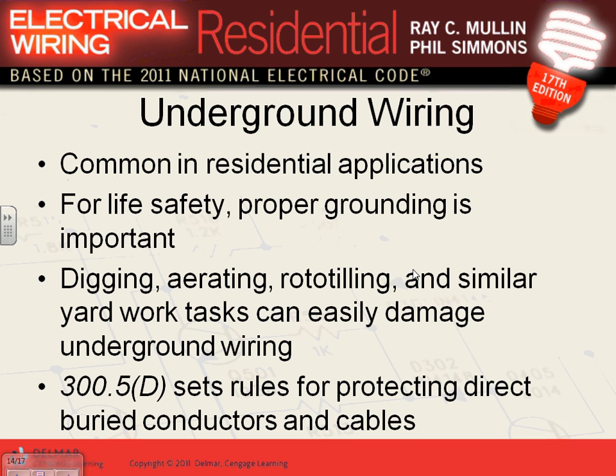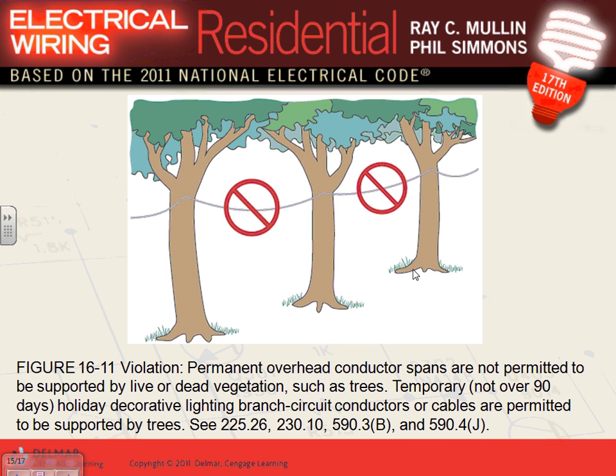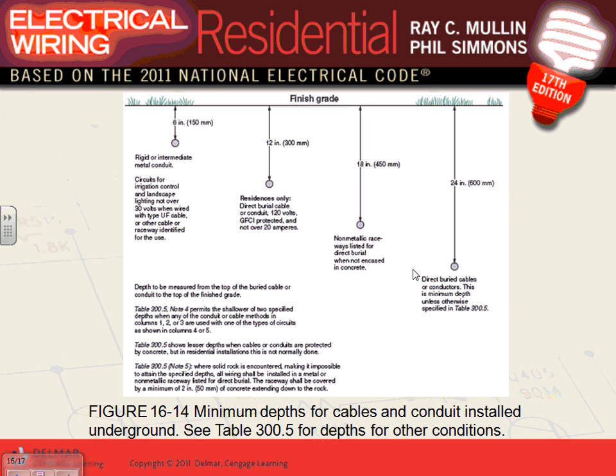Okay, underground wiring. There's a table that we'll talk about for the underground wiring. Here's what you cannot do. If I have a shed on my farm, can I use the trees to take the power lines to the shed? It would be nice. I've seen people doing it, but not according to the code. Tree to tree to tree, you can't. Feeders, branch circuits, or service conductors. Remember the 3 circuits? You cannot. No, no, no. That brings us to this table.